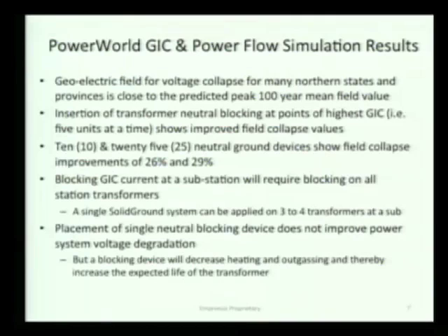So we did a run with one unit, and you see very little difference on voltage collapse, not much at all, for one transformer. But of course, remember, if that's an older transformer, you're going to extend its life. It's not going to be carrying GIC, and so the transformer is going to last longer.